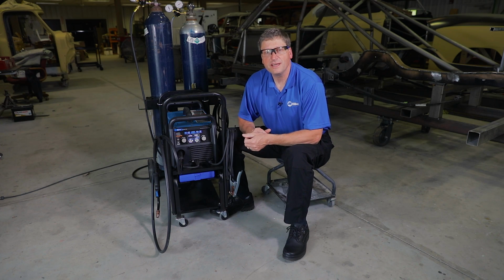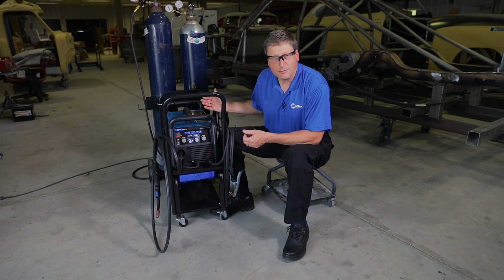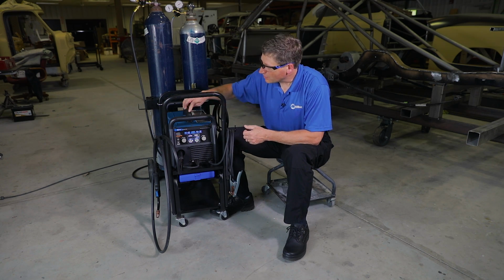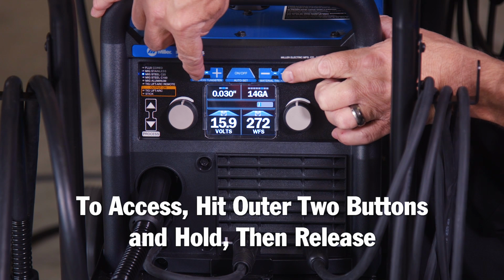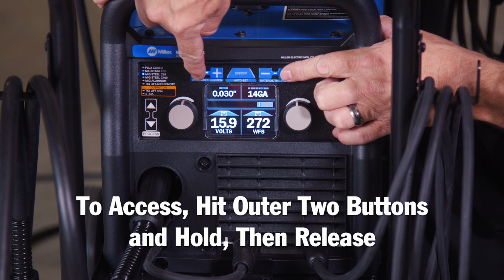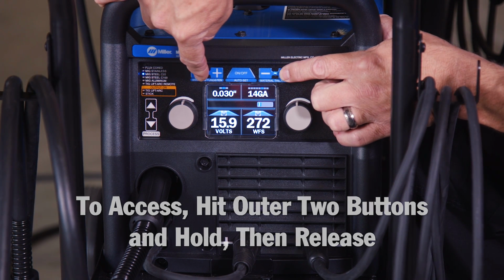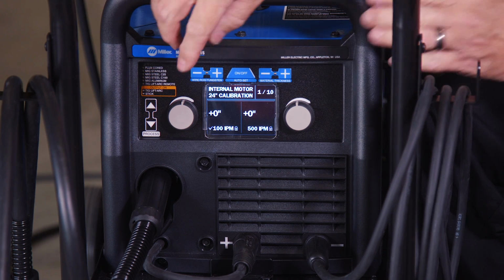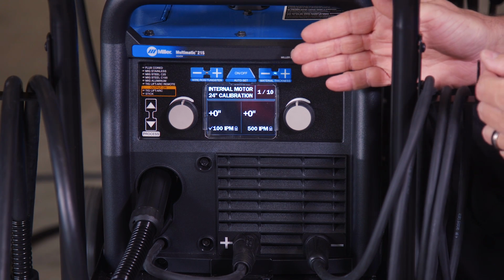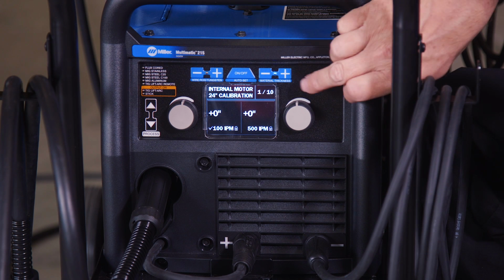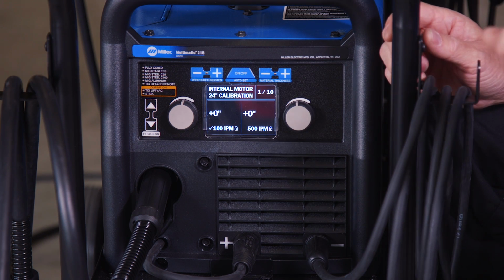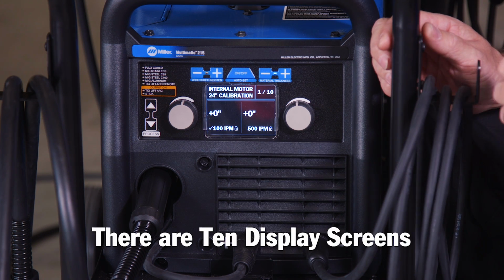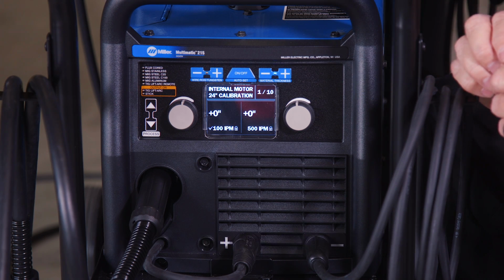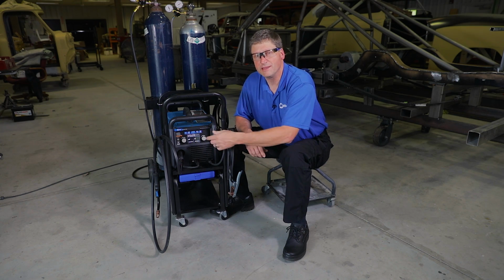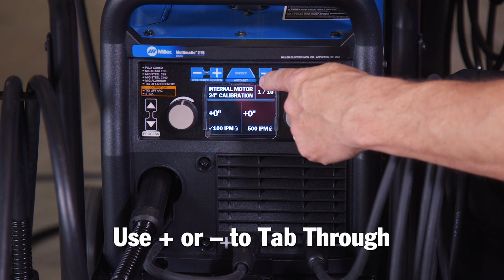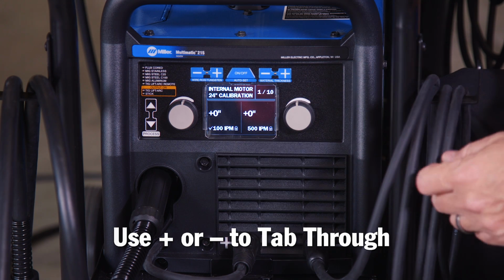First, to get into the hidden menu screen, obviously the machine's got to be turned on, and you're going to want to be hitting the outer two buttons at the same time for a couple seconds and then release. That's going to bring up a new window on the digital screen. You'll see in the upper right hand corner, this is screen 1 of 10. There's 10 display screens in this menu setting. We can tab through those menus by either hitting the plus or the minus button of the material thickness settings.